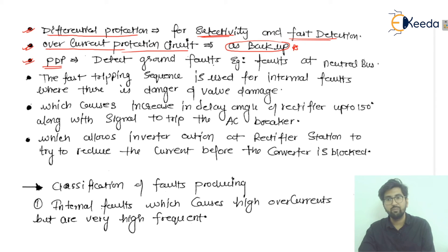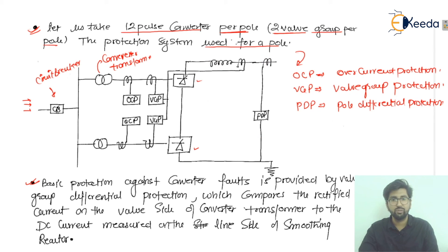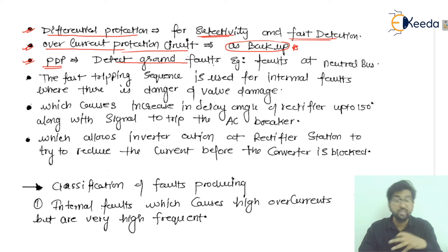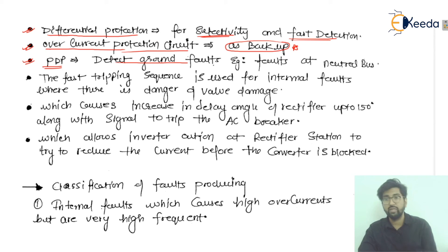PDP stands for pole differential protection, connected between these two points. It detects ground faults — for example, faults at the neutral bus. Detection of ground faults is sometimes not possible otherwise, so PDP is used specifically for detecting ground faults at the neutral bus.